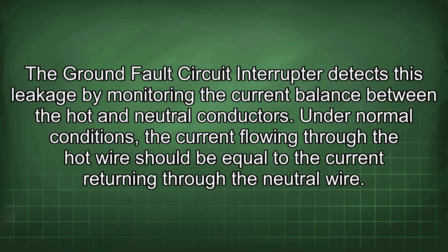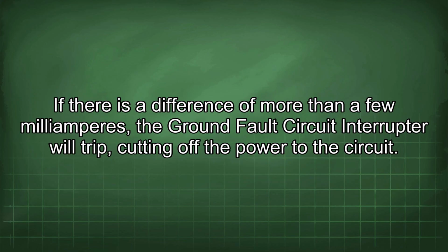The ground fault circuit interrupter detects this leakage by monitoring the current balance between the hot and neutral conductors. Under normal conditions, the current flowing through the hot wire should be equal to the current returning through the neutral wire. If there is a difference of more than a few milliamperes, the ground fault circuit interrupter will trip, cutting off the power to the circuit.